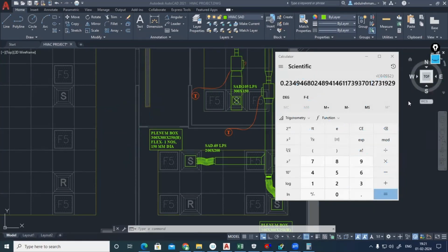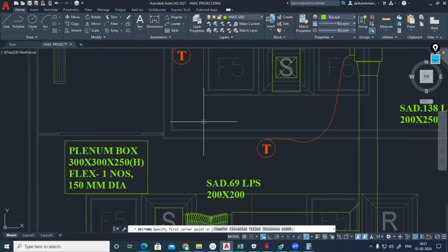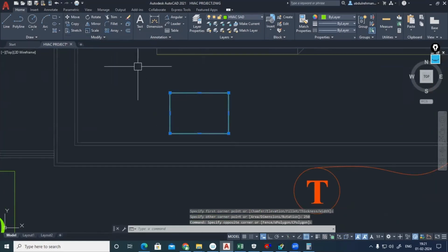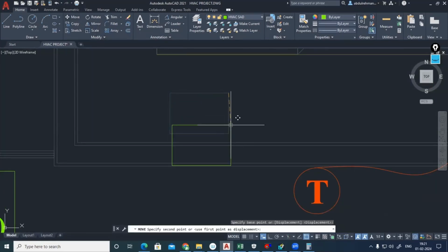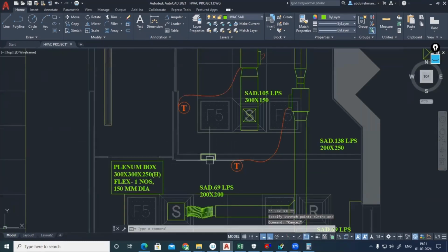250 wall opening, you have to show. Correct. There is one option, 250. It means you can take an opening somewhere here, like 250, which means the width will be 250. The length simply has to be arranged as per the wall. Move it, just as per the wall. Now you can simply mark that as WO 250. Okay, wall opening. Or you can arrange a transfer air duct.